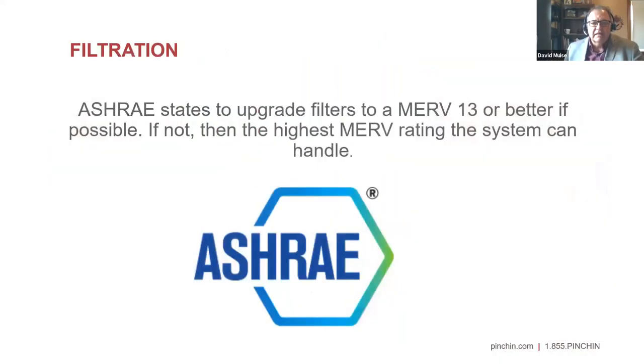So ASHRAE states, when they talk about filtration, to upgrade filters to a MERV 13 or better if possible. If not, then use the highest MERV rating the system can handle, because not all ventilation systems were designed to handle a MERV 13, but that is the ideal.